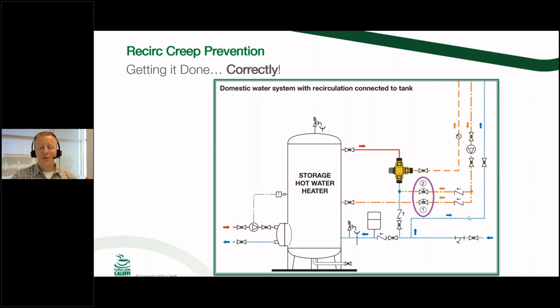Okay, so with that in mind, you're going to want to set this valve here, valve number 1, to basically eke by enough flow through there to go through the tank, and then add just enough heat back into the mixing valve to bring that loop back up to whatever temperature you want it set to, so 120 degrees or whatever. But you're going to need a very specific scenario in order to accomplish this.